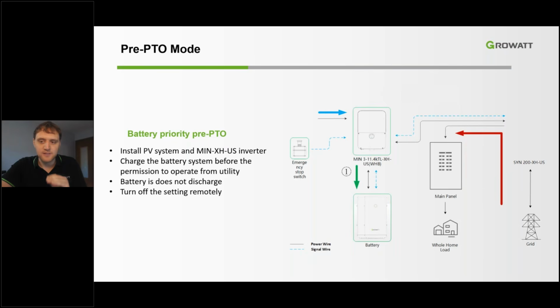Another great aspect of this is the Pre PTO function can be remotely disabled. Once the interconnection approval is granted from the utility, the Pre PTO function is disabled through our OSS app, and it's able to create a more reliable means of starting your customer system. Your teams are going to immediately start the operation of the inverter and impress the customer with timely service.